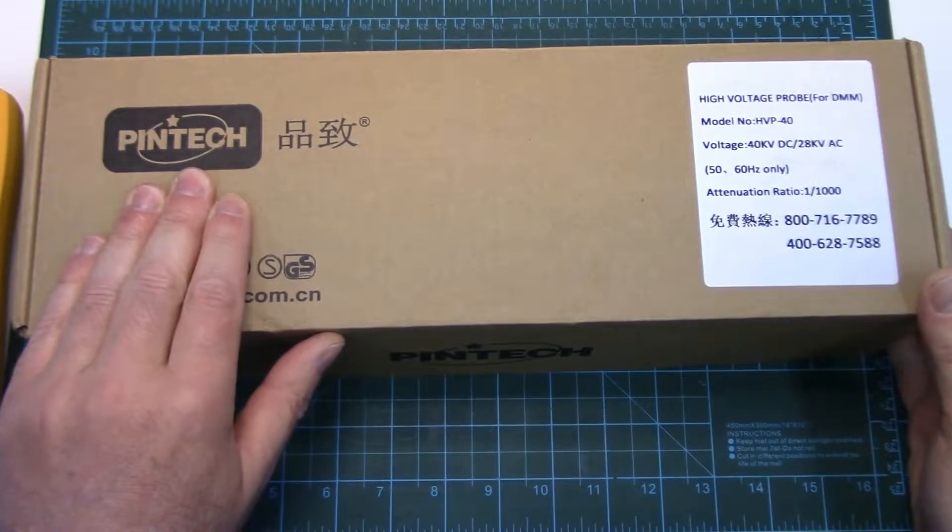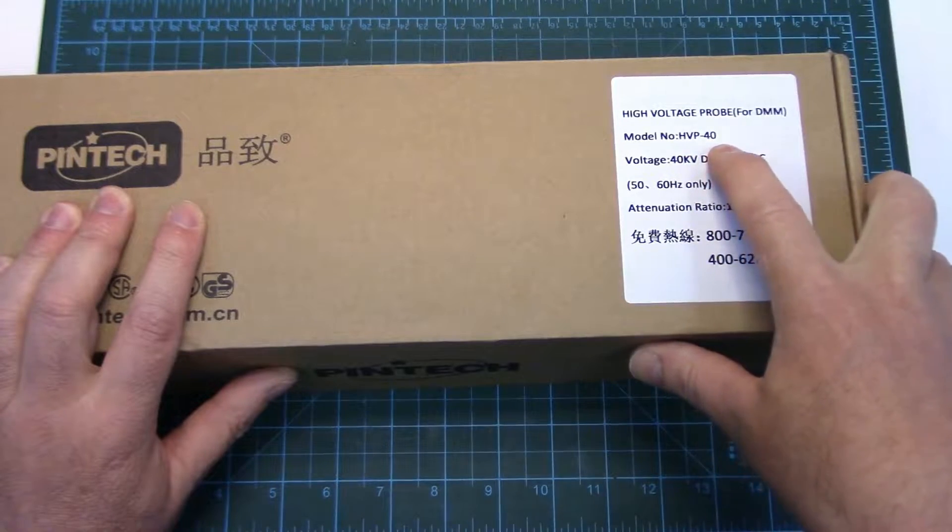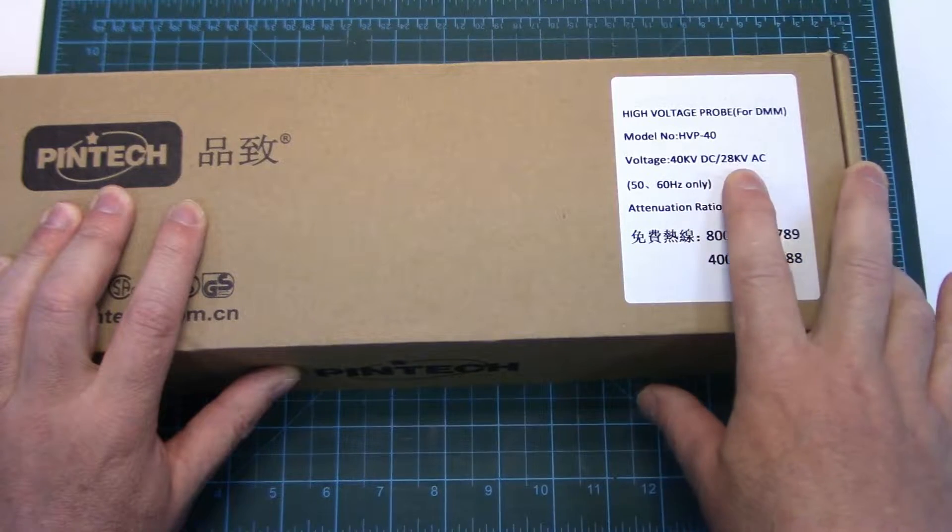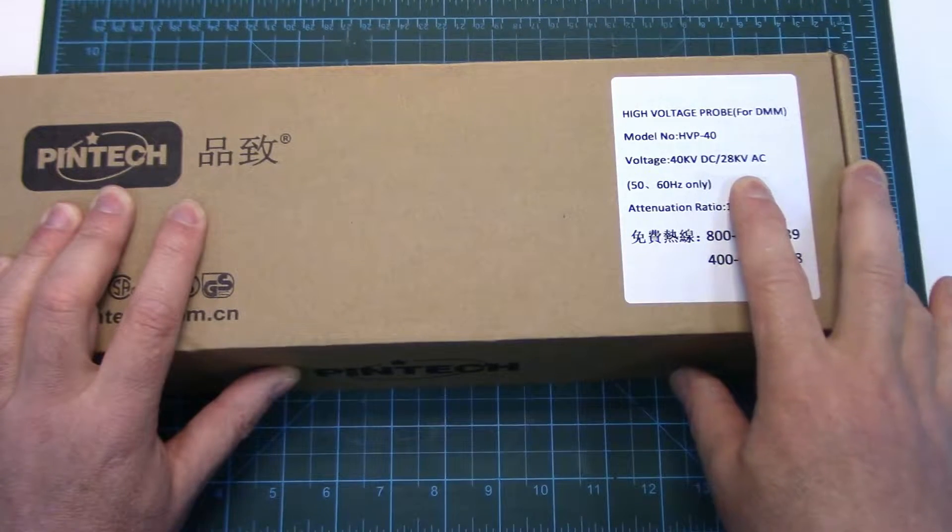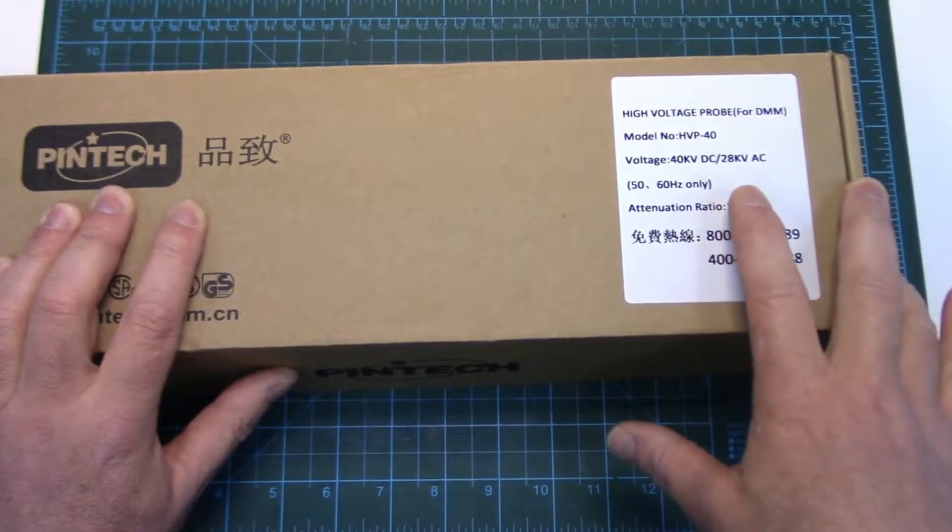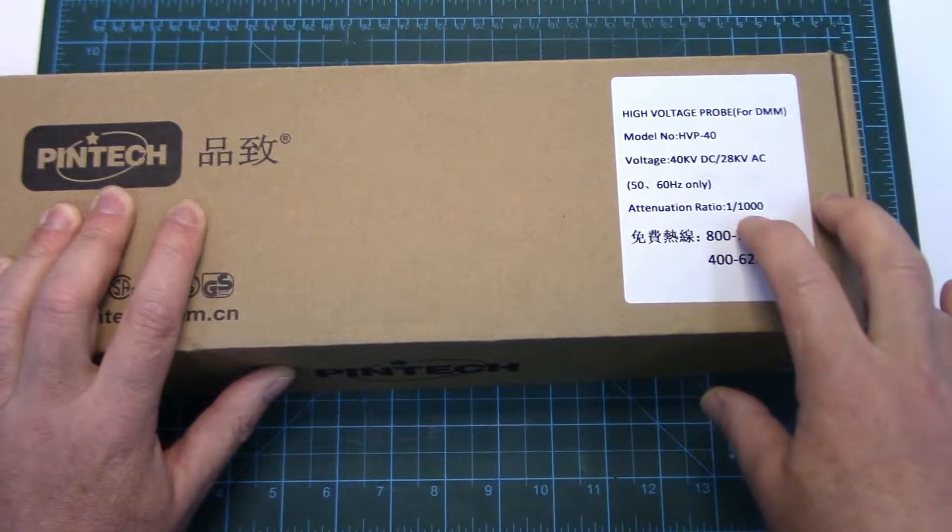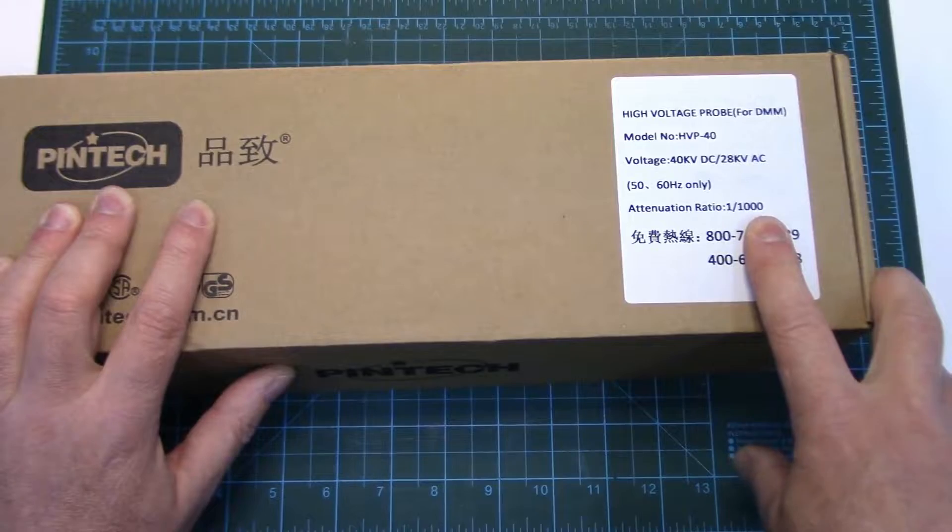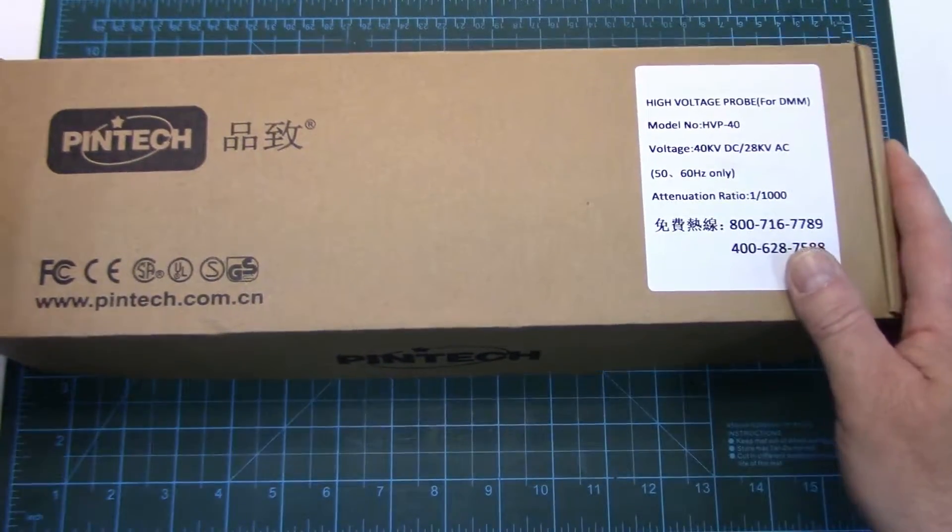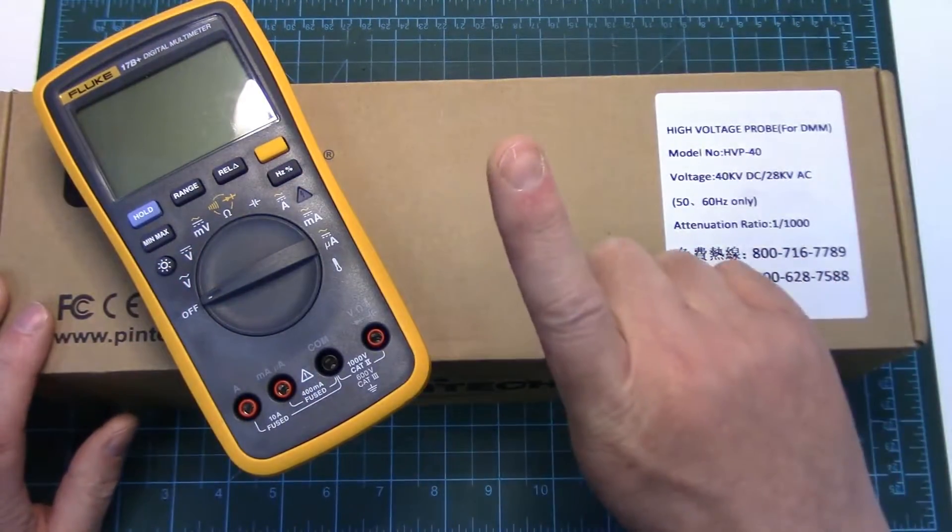This specific one is made by Pintec. It's their model number HVP40. The voltage range will measure up to 40 kilovolts DC or 28 kilovolts AC. In AC it does from 50 to 60 Hertz, so basically line type voltage frequencies and the attenuation ratio. All high voltage probes like this are very similar. This one's 1 to 1,000, meaning that for every 1,000 volts that you probe with the high voltage probe, your digital multimeter will read 1 volt.